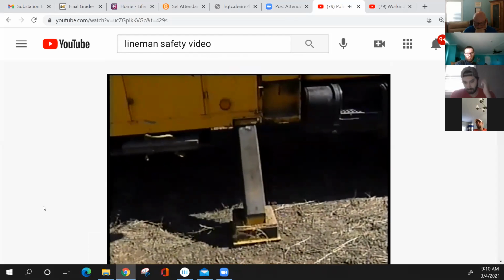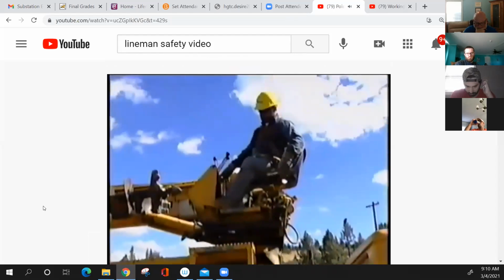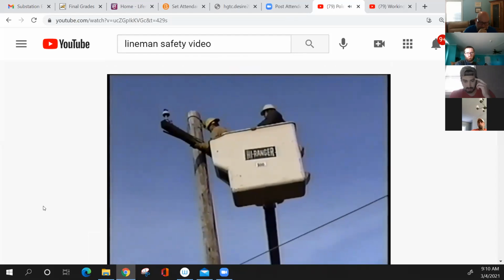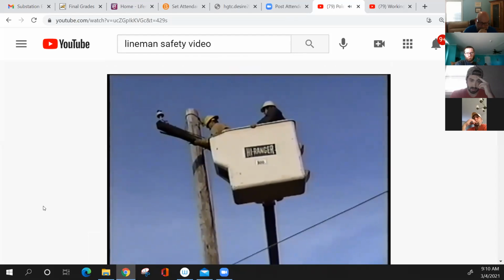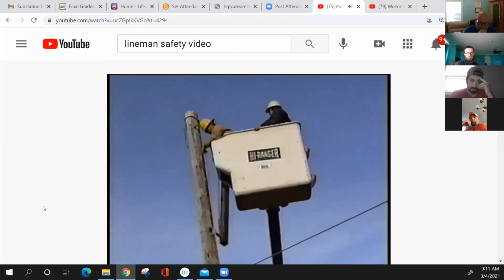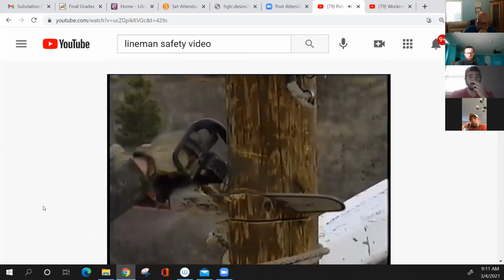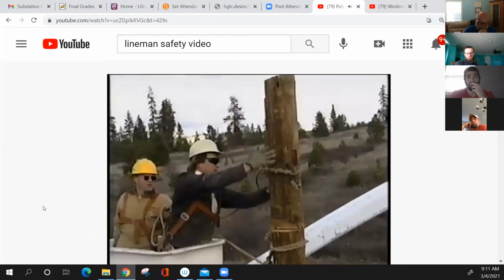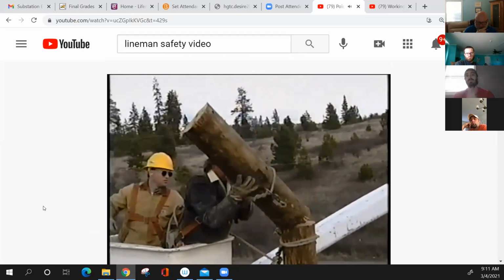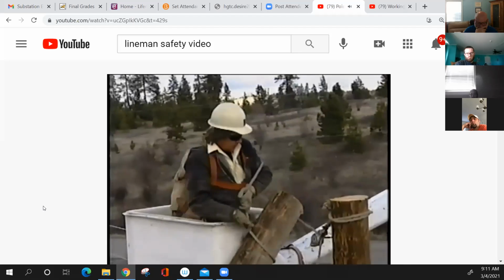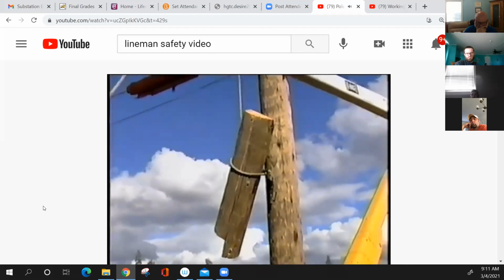After the bucket truck is positioned safely with outriggers on level, stable ground, all hardware and attachments are removed and lowered down on the hand line or with the boom of the line truck to reduce weight on the pole. A piece or chunk is cut off the pole in a section small enough for an employee to remove and lower with the hand line. This process continues until the pole is cut down to the desired height.